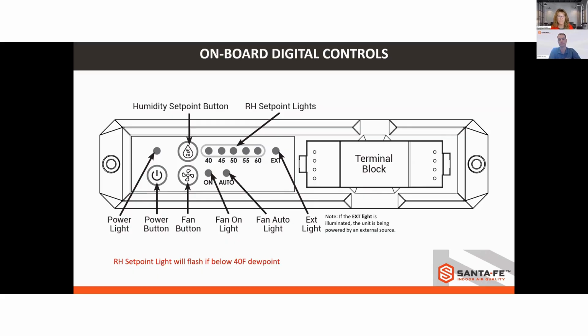So we've kept it in increments of 5 just because we know a lot of times when we have hygrometers in our homes that there's going to be a discrepancy in what those potentially are reading and what we've got the unit set at. So that way it helps prevent any callbacks if you set it at 55 and the homeowner is saying it's 58% RH in my house. So that gives us a little bit of leeway there.